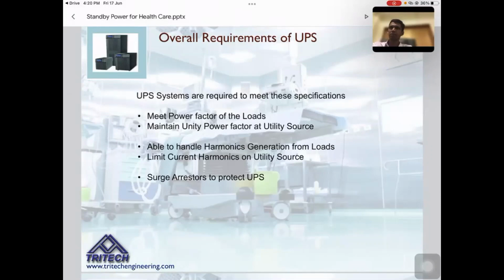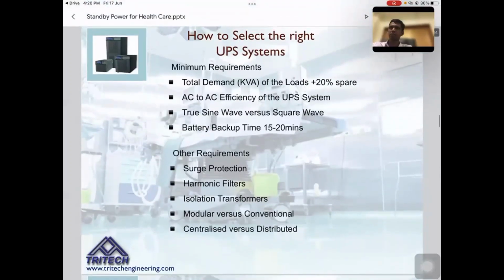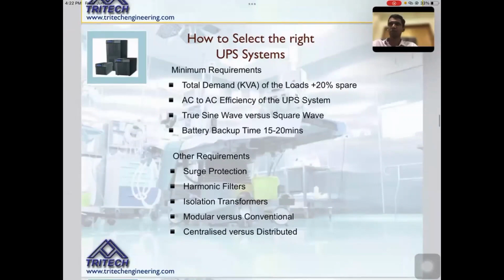And of course, there are the harmonics which need to be addressed, and also surge arresters are required to be connected to the UPS, which will protect the UPS from external surges. So basically, these are some of the requirements that you need for the UPS. Now, how do you select the capacity of a UPS? To select a UPS, you need to find out the connected load, then work out the demand load that is coming on the UPS, and then add a spare capacity. You should also look at the AC to AC efficiency.